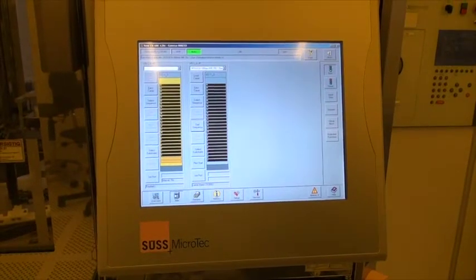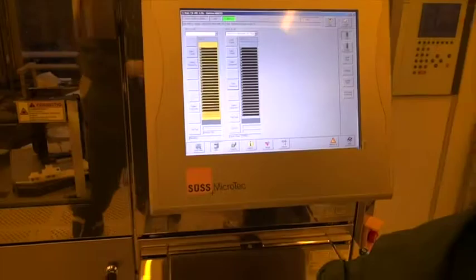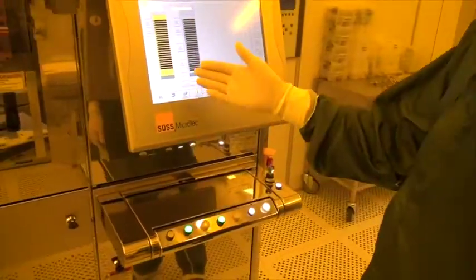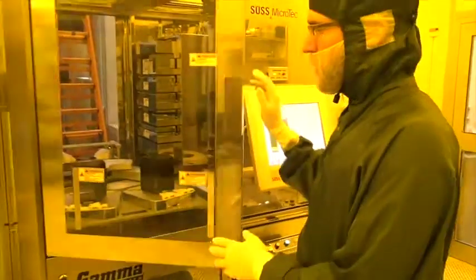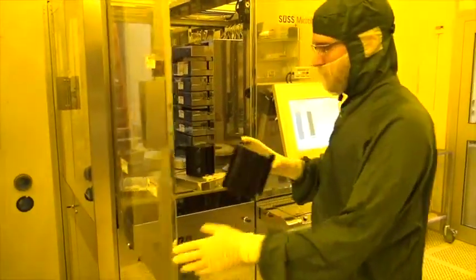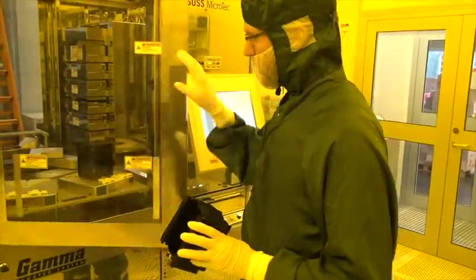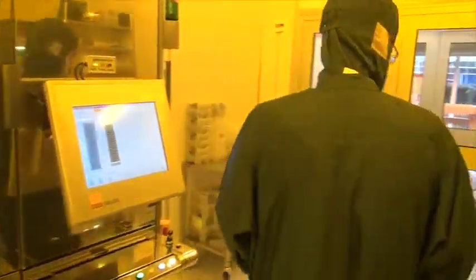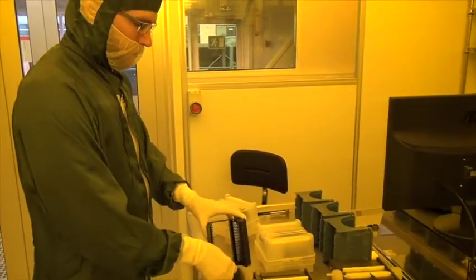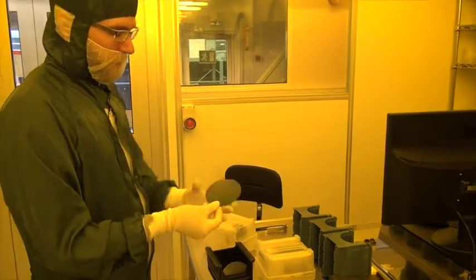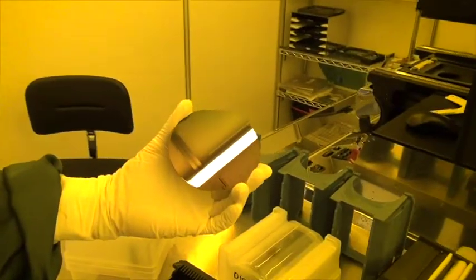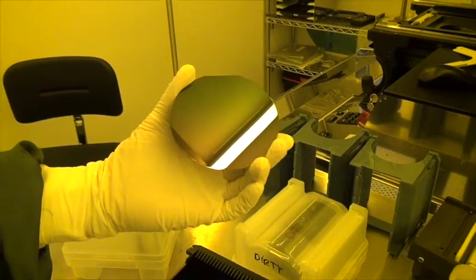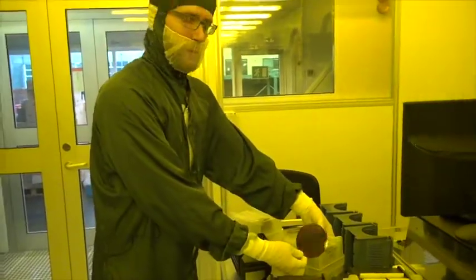When the dummy wafers have finished we can unload the cassette and notice that the order of the wafers has been reversed in the output cassette. So they are now at the bottom. We can inspect the dummy to see if the coating was successful. If we are happy we can continue loading our own substrates.